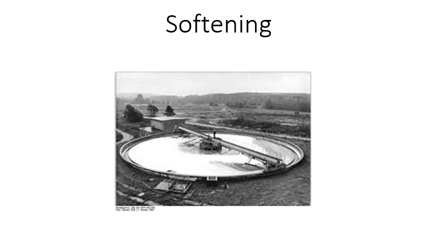Alright, some keynotes about softening. Excess lime or soda ash is primarily used if non-carbonate hardness is high. So excess lime or soda ash is used for non-carbonate or permanent hardness if it's high. Lime softening is for carbonate hardness, temporary hardness. Split treatment can be used in waters high in magnesium. The pH of water after softening can be very high.